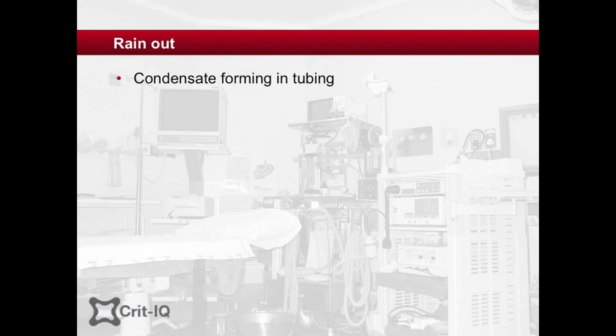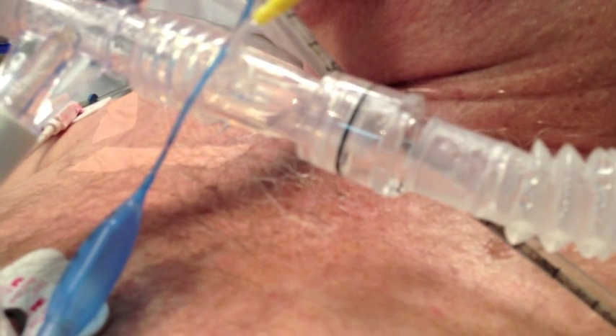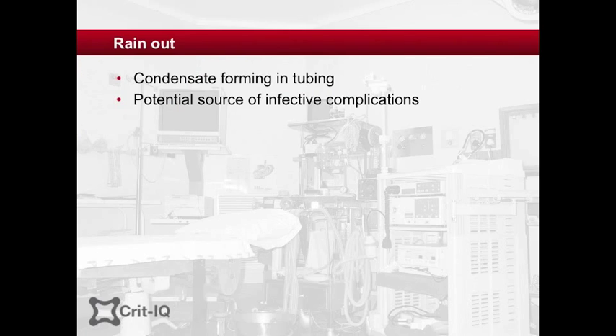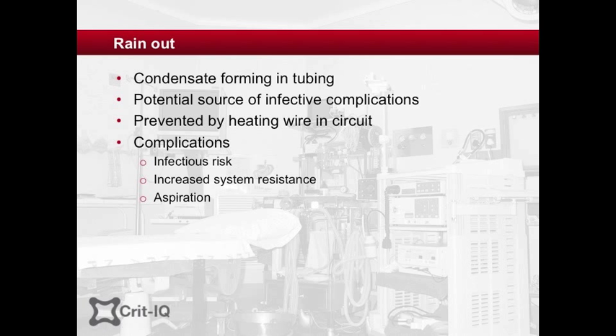Humidifying the circuit can result in condensation forming in the tubing, a phenomenon known as rain-out. Rain-out has been suggested as a potential source of microorganisms that can lead to ventilator-associated pneumonia. To combat this, some circuits include a heating wire that prevents gas cooling and condensation from forming. Rain-out should never be allowed to drain back into the humidifier as this exposes the patient to potential infection. It may also increase resistance in the circuit, interfering with ventilation, be accidentally aspirated by the patient during turning, and even trigger the ventilator — an event known as auto-triggering.